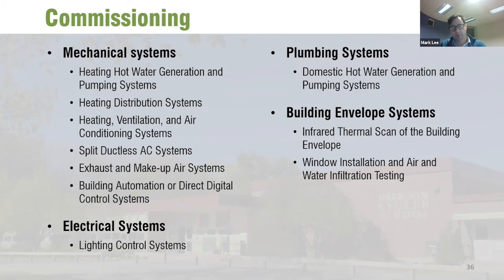So we'd go through and confirm, yep, you installed the system, and from everything we can see, it looks to be installed and operating. What we wouldn't do is test all the airflows and put it through a whole bunch of different scenarios to understand if it's responding correctly to all these operation modes. That optimization of the equipment isn't something the designer of record takes care of, so you may get all this equipment, but it may not be optimized to run as efficiently. That's the slide showing 8 to 30% more efficient operation by having systems commissioned, so you could have more operating costs than if the systems were commissioned on the mechanical and energy side.